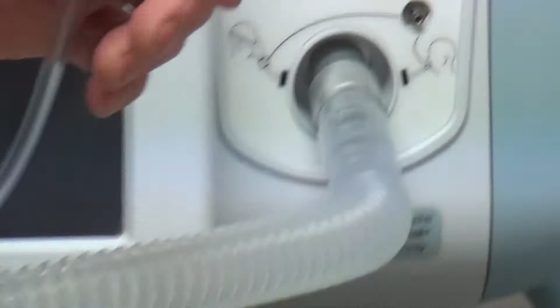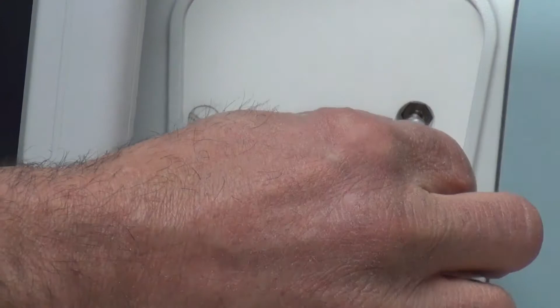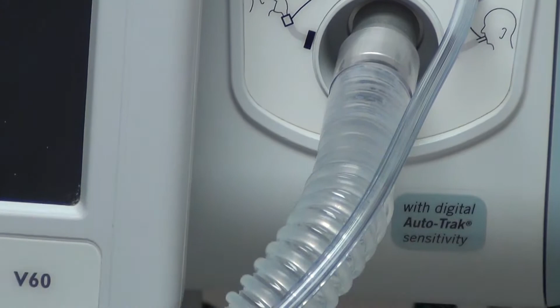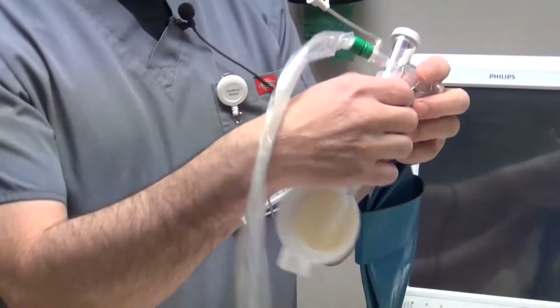And I'm going to plug in the large tubing, and then this small tubing is for monitoring pressure. So I'm going to plug it into this little port right here, and it is a little tough to put on, but you can manage. At this point, you would connect the same connections you used on the other ventilators. You're going to connect your HME, your Ballard or suction, and again it unplugs here and it unplugs here. There we go. You plug that in here, and you would connect it to the end of your circuit, just like that.